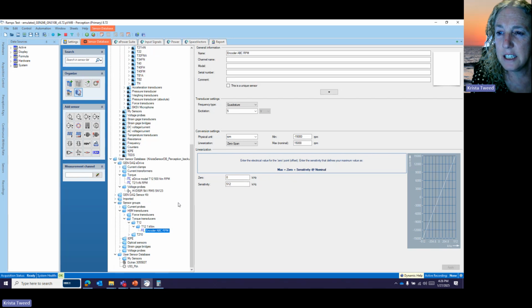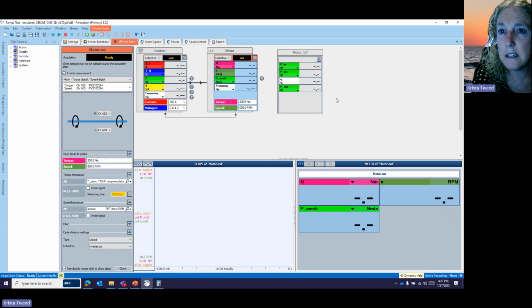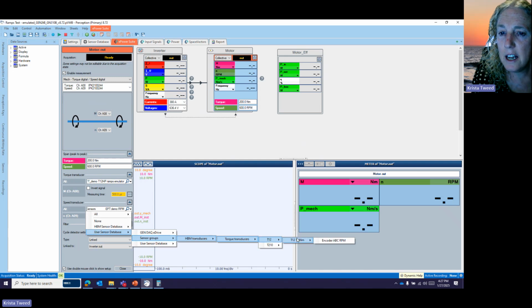And now that sensor is down in my user sensor database, still under HBM transducers and T12. I could move that to be somewhere else if I wanted to, but there's my new sensor that now when I go to set up my motor in the ePower suite, I will look at the motor. If I click on the speed sensor under user sensor database, sensor groups, HBM transducers, torque transducers, there's my encoder that I created, and I could then select and use it for that channel.